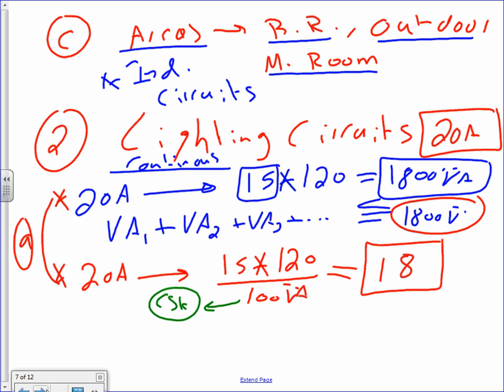Or you use a design rule of thumb, which is to take the 15 amp, multiply by 120, and divide by 100. Where did the 100 come from? 100 volt amp. A typical fixture like this is typically around 96 volt amp. How do I know? Because we install them all the time. So on average, especially with the energy code right now, this is even very high.